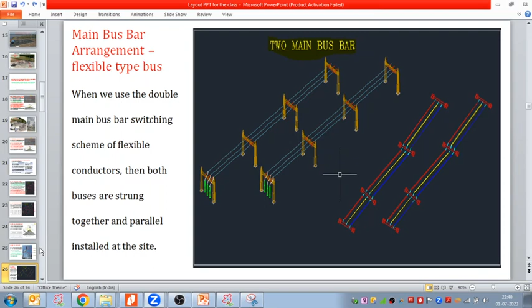So when we use the double main bus bar switching scheme of flexible conductor, both bus bars are strung together and installed parallelly at the site. Now, coming to the bus bar with double main bus bar, transfer bus bar and the reserve bus bar, how do we do it? First of all, both bus bars will come together. In the double main and transfer bus bar scheme, both bus bars come together, plus the transfer bus or the reserve bus will come near to the entry or exit point of the line bay, not at the trafo bay, at the line bay, right?